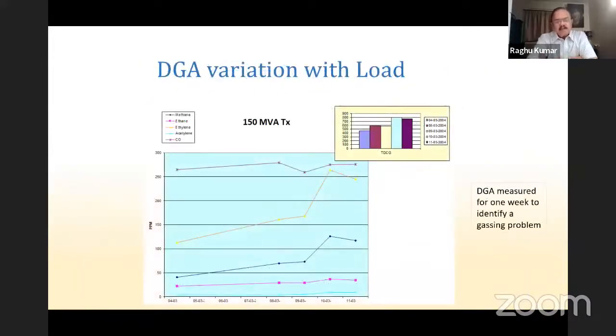This is a practical example of monitoring success. This was a 150 MVA transformer, and it was giving Buchholz alarms. The gas was not sufficient to trip, but it was creating Buchholz alarms. When you reduced the load, the alarm was disappearing. This was a very important transformer, and we couldn't switch it off immediately.